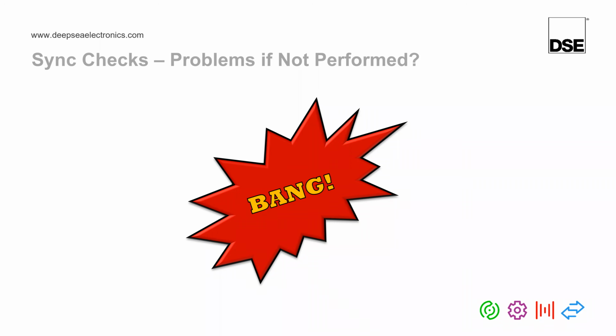So lots and lots of times people will call us at DeepSea and say, I have a generator system where the load sharing is unstable. What could be the problem? Well, as you can now see, the problem could be something with your governor or AVR. It could be something with the CTs. It could be something with the MSC link. So the 4 steps to synchronizing is not just a commissioning procedure, it is also your fault finding procedure.